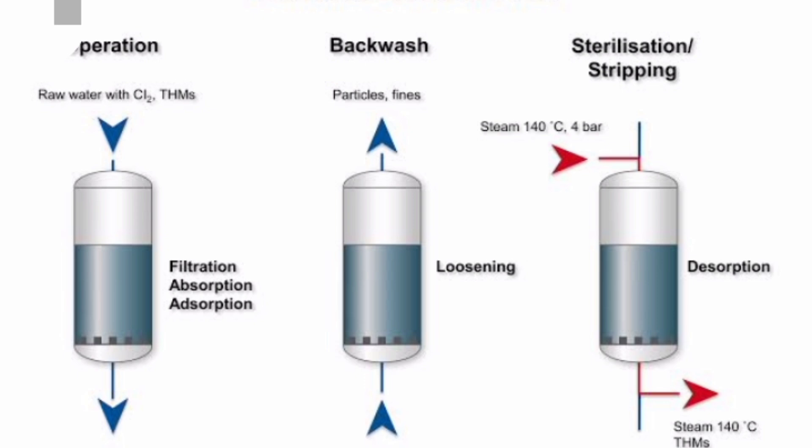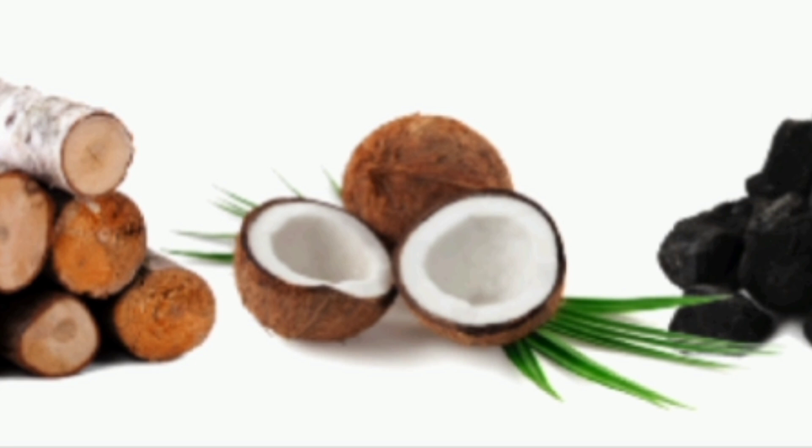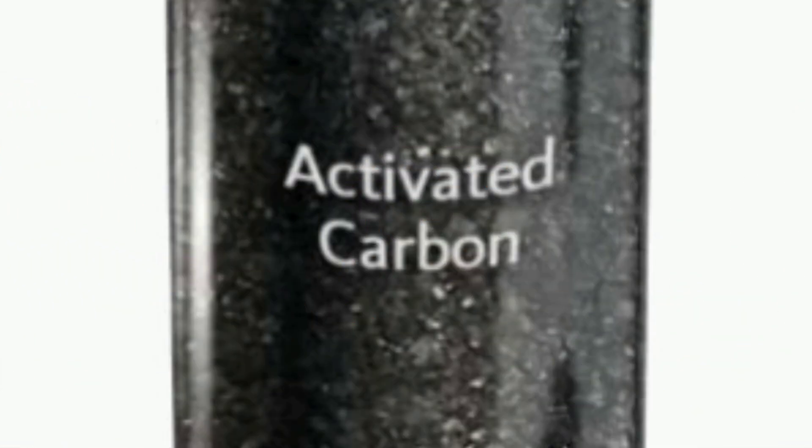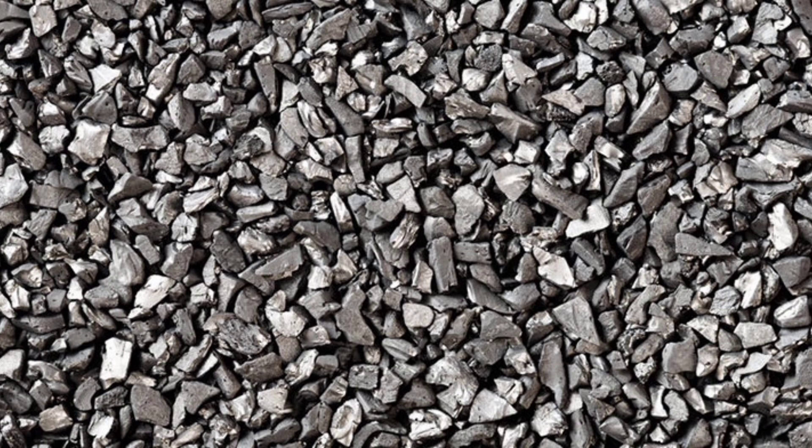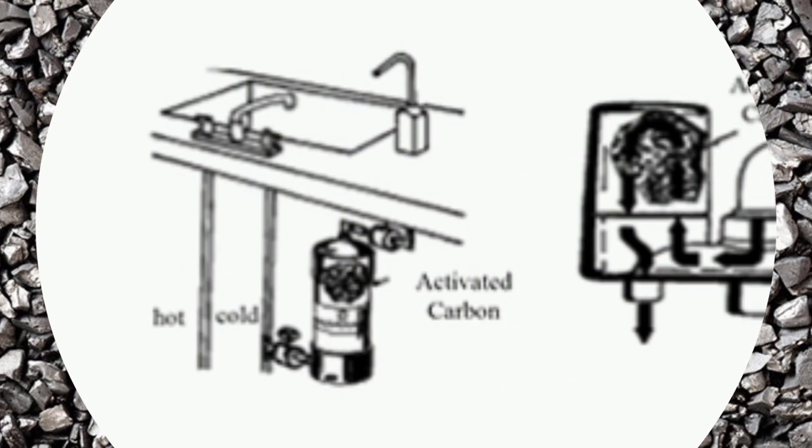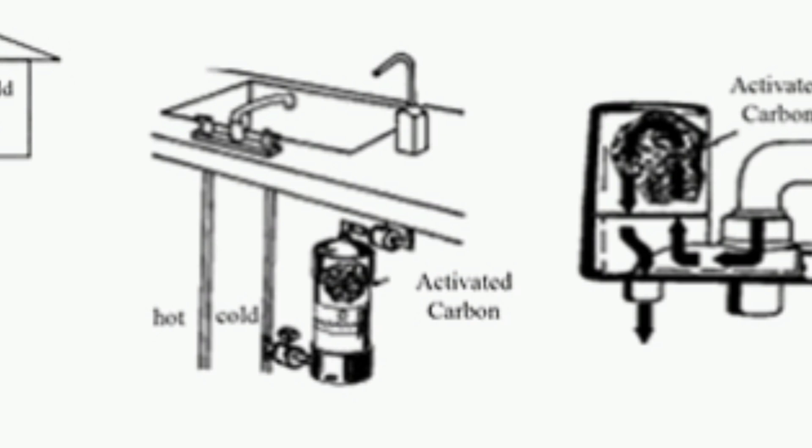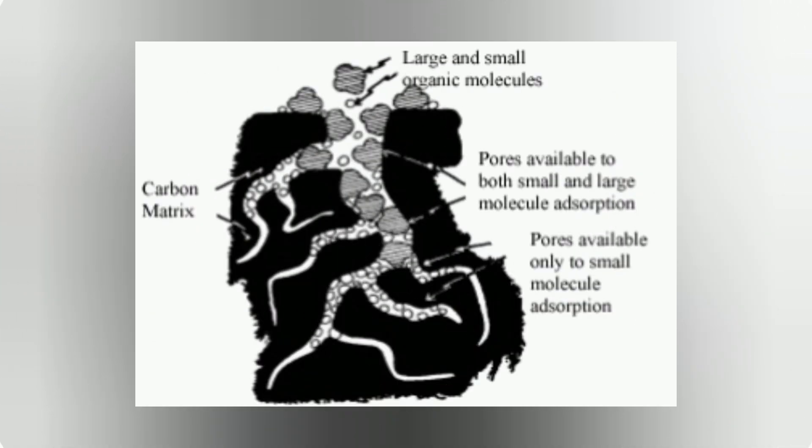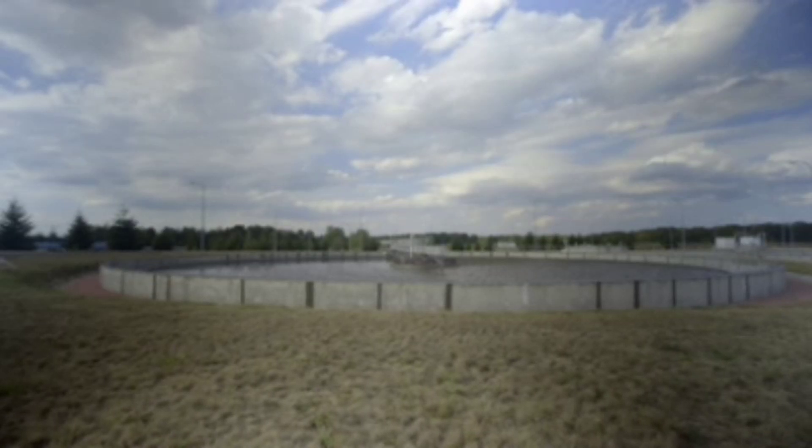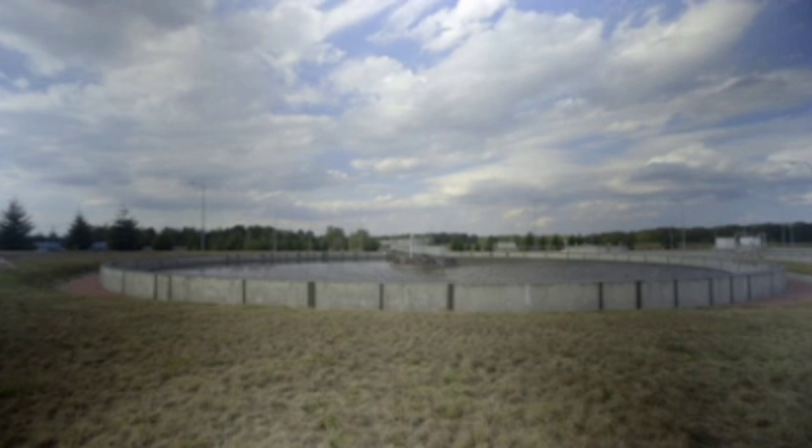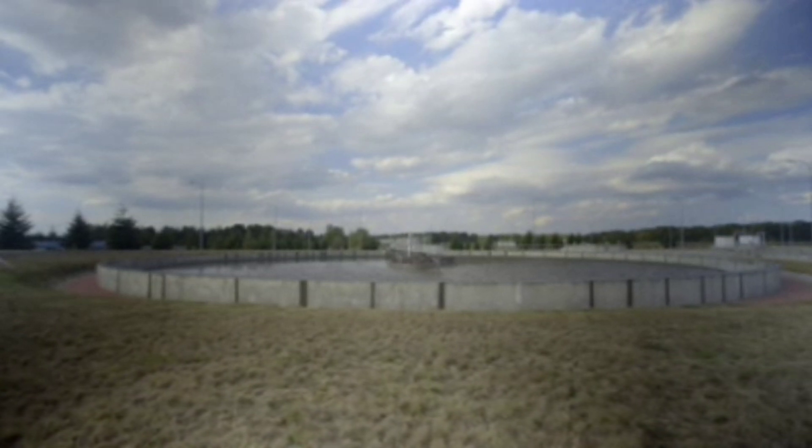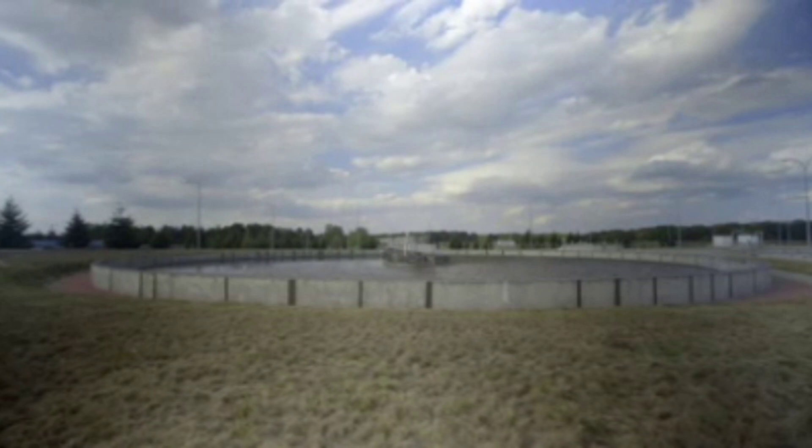In laboratory water purification, activated carbon is used in pre-treatment to remove free chlorine and chloramines from the feed water to reverse osmosis membranes and to remove trace organic impurities from water. In larger systems, cylinders of activated carbon may also be used to absorb larger quantities of organic impurities. Its major use in pre-treatment is to remove free chlorine and chloramines before reverse osmosis to prevent membrane damage due to oxidation. Activated carbon reacts very rapidly with free chlorine in water to produce chlorides. A relatively small volume of carbon can be effective. Over five times the volume of carbon is needed to catalyze the removal of chloramines.